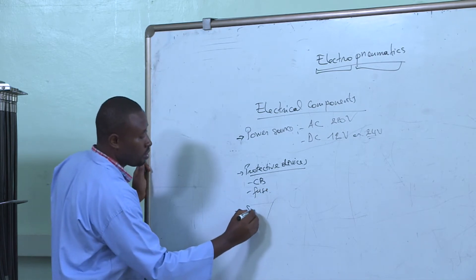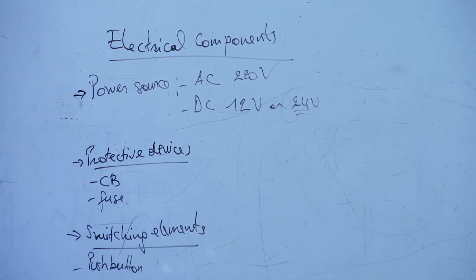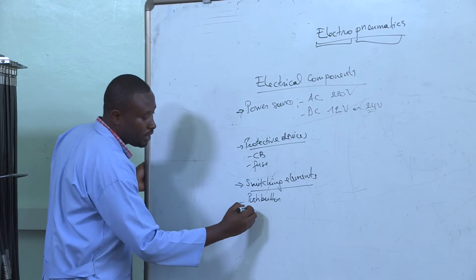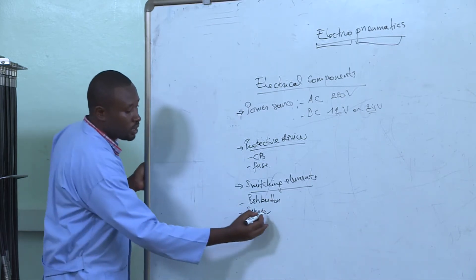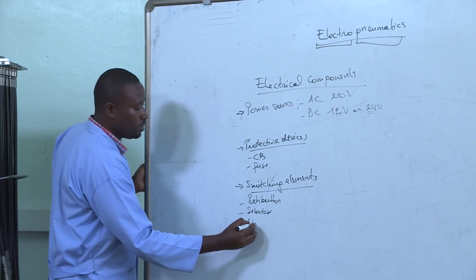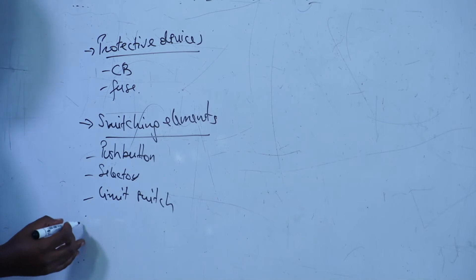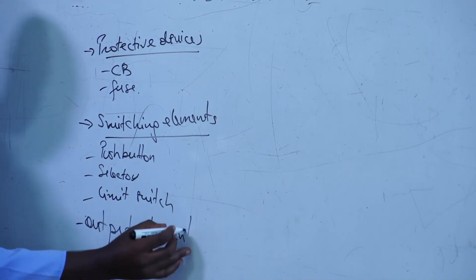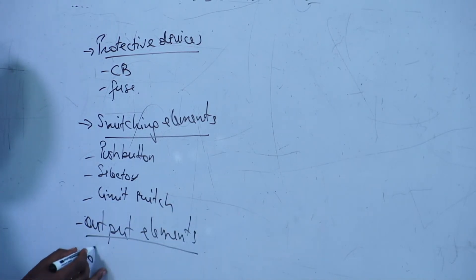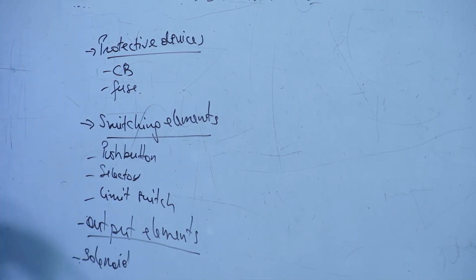We will also need switching elements such as a push button switch, a selector switch, and limit switches, and so on. We also need to have output elements — for example, the solenoid. This solenoid is connected to the pneumatic valve and is the one that controls the pneumatic valve.